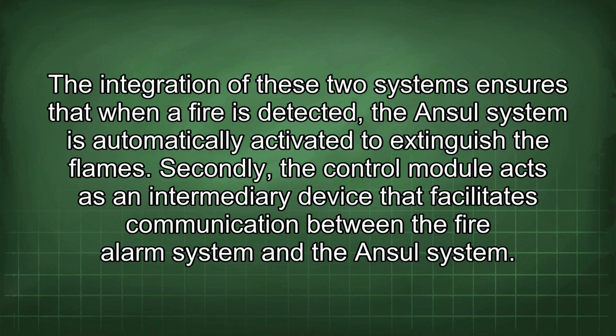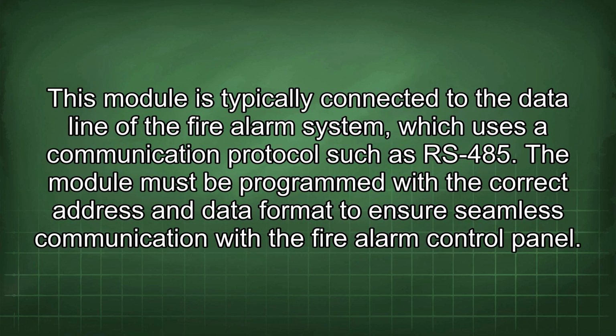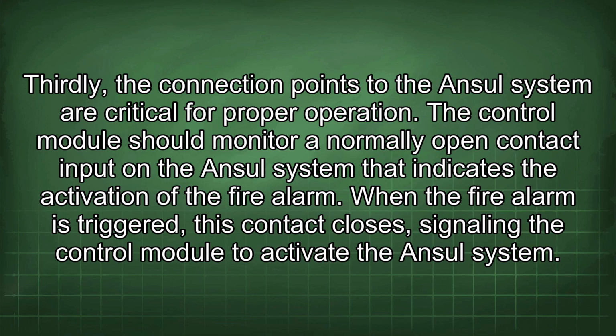Secondly, the control module acts as an intermediary device that facilitates communication between the fire alarm system and the Ansul system. This module is typically connected to the data line of the fire alarm system, which uses a communication protocol such as RS-485. The module must be programmed with the correct address and data format to ensure seamless communication with the fire alarm control panel. Thirdly, the connection points to the Ansul system are critical for proper operation.